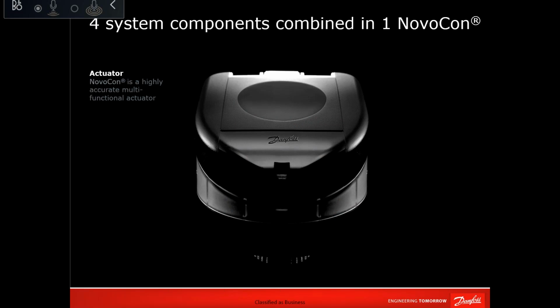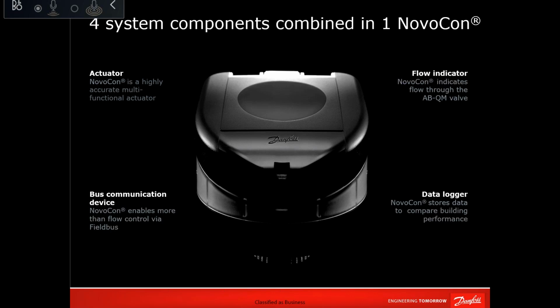So Novocon is an electronic actuator which can give us these features: bus communication through BACnet MSTP or Modbus RTU, flow indication, data logging through a trend system from the BMS, which means usually an actuator will receive a hardwired control signal and will give you a feedback signal in terms of 0 to 10 volt or 4 to 20 milliamps. In case of the smart actuator, every single variable inside this actuator can be addressed, and you can read it or you can write it or both.